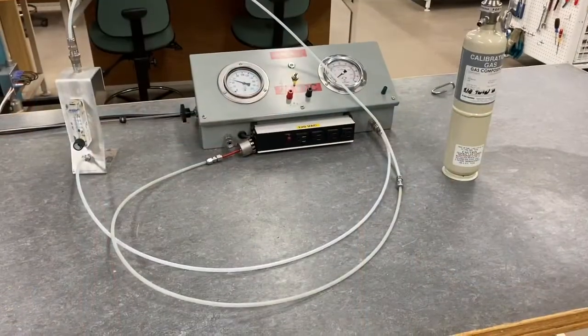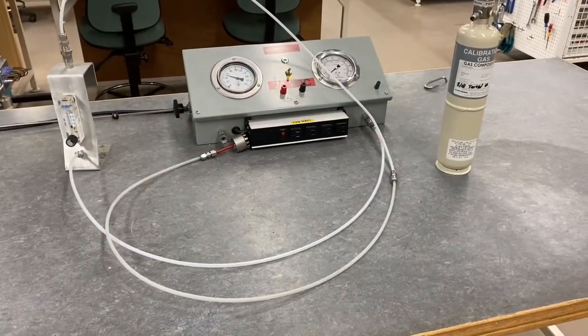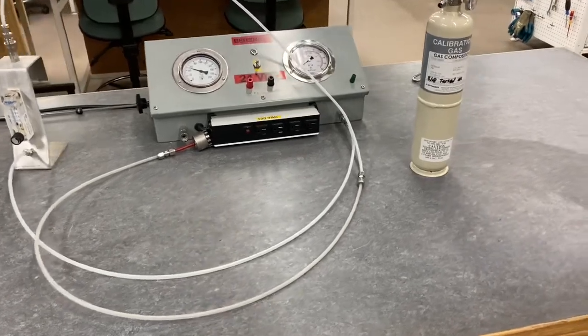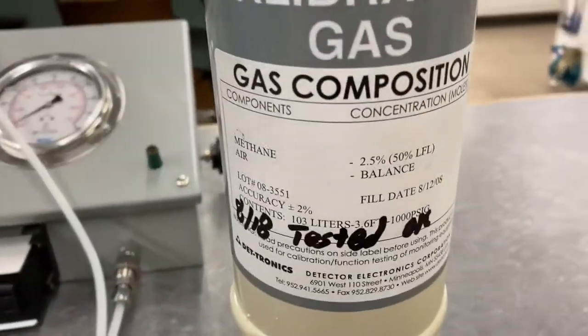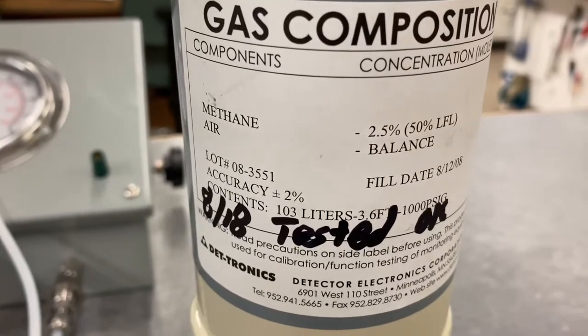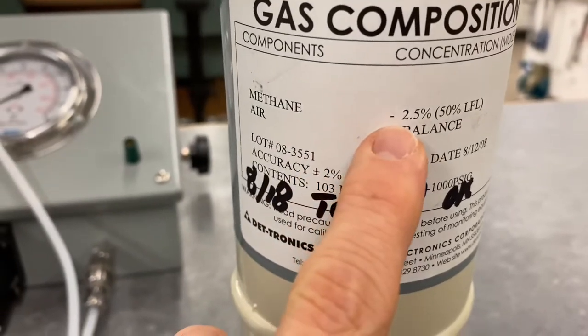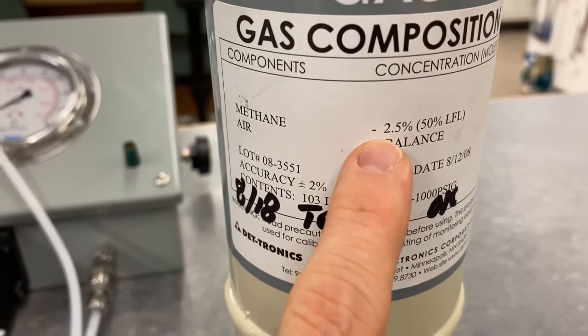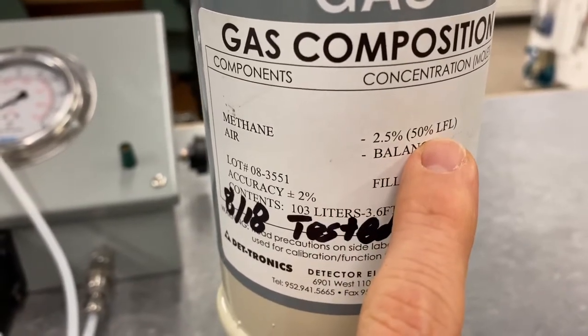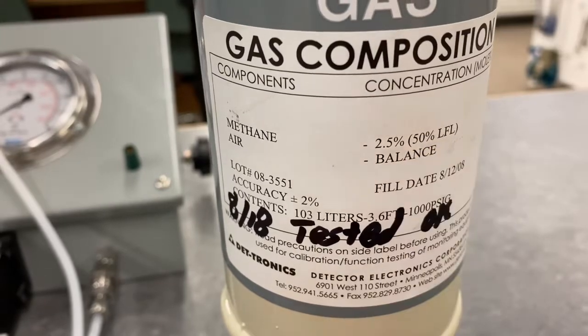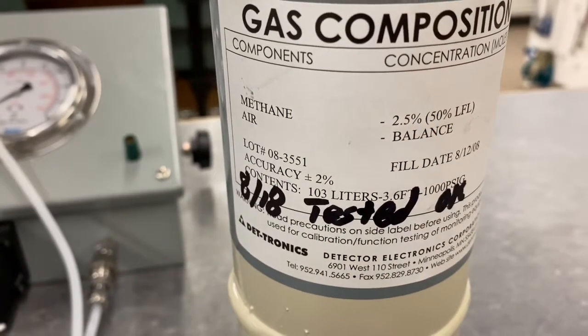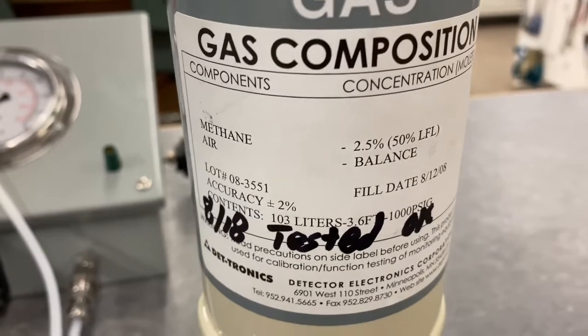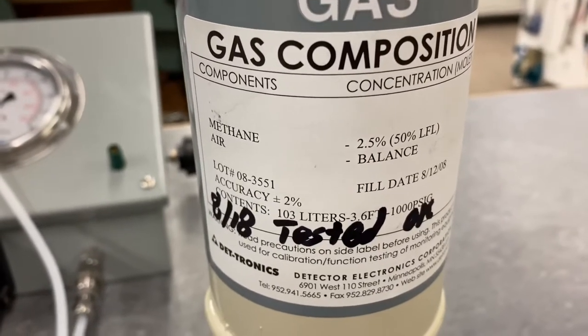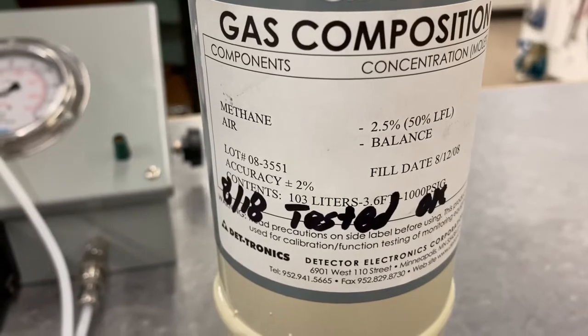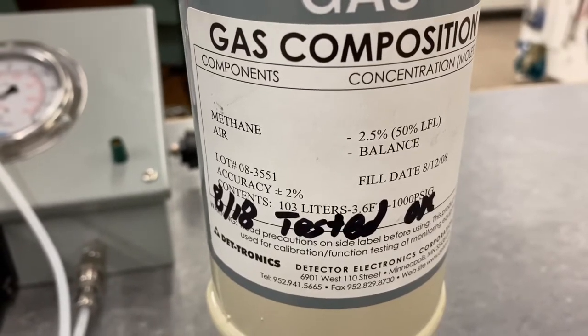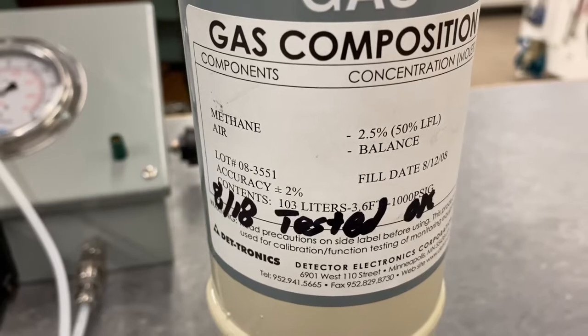So I've got similar equipment here that we used for the toxic gas sensor, the electrochemical cells lab. But this time around our calibration gas is different. We're using methane balanced with air. And you can see that the concentration of methane here is 2.5%, which is 50% of the LFL, lower flammable limit, or quite often the term we typically use in class and here in Canada is LEL, which stands for lower explosive limit. So this is going to be our calibration gas this time, a little bit different, but pretty well very similar procedures will apply.